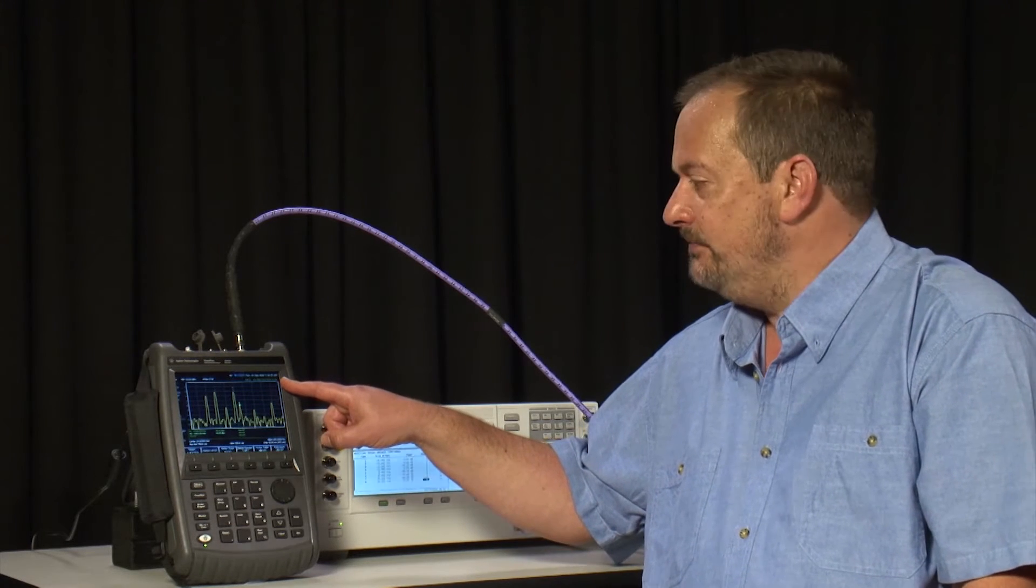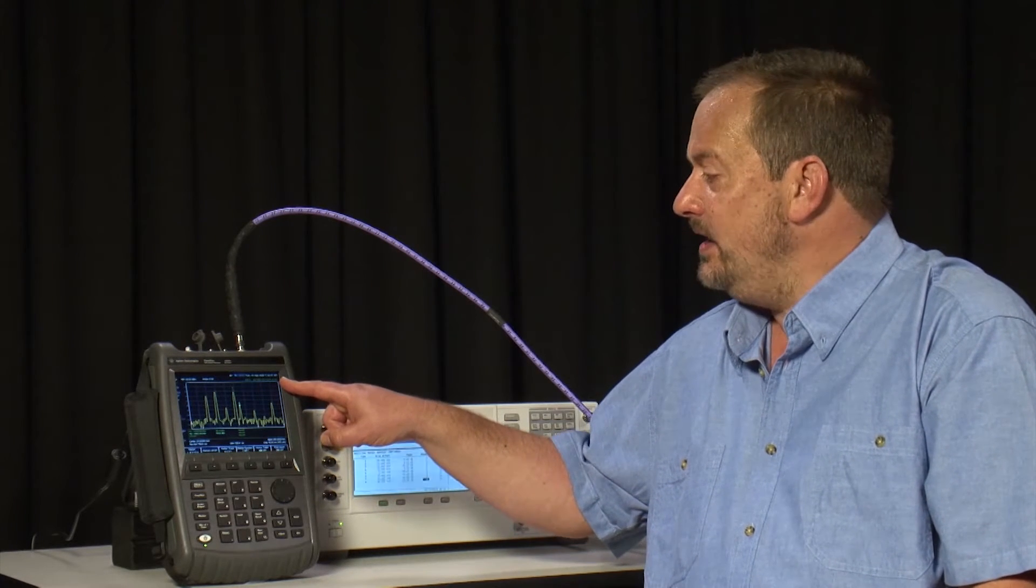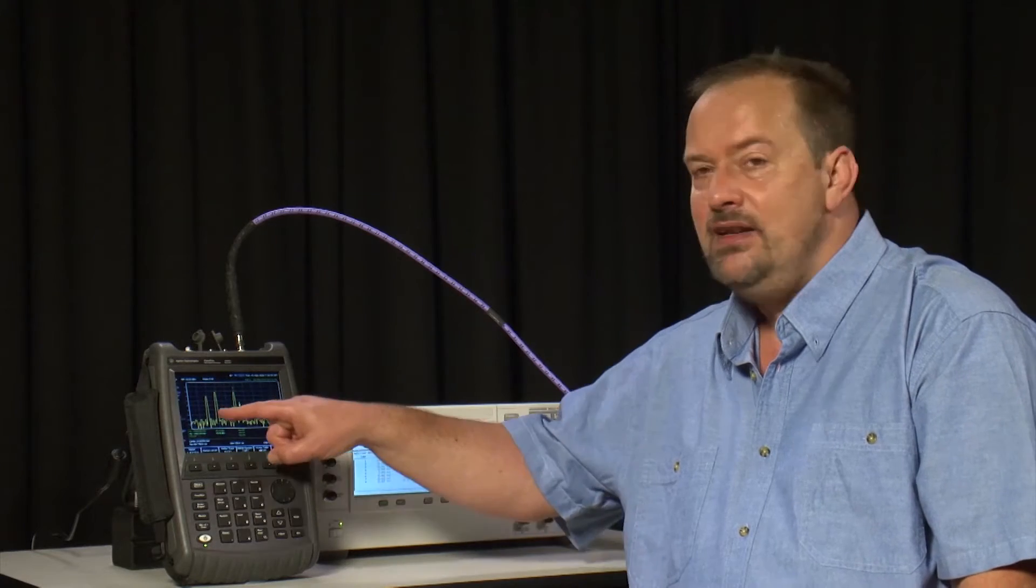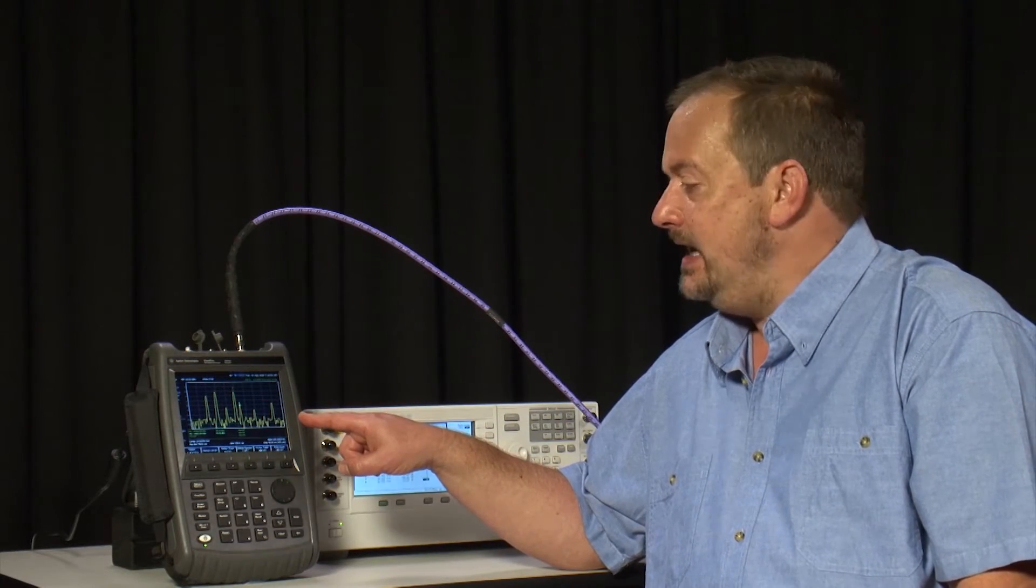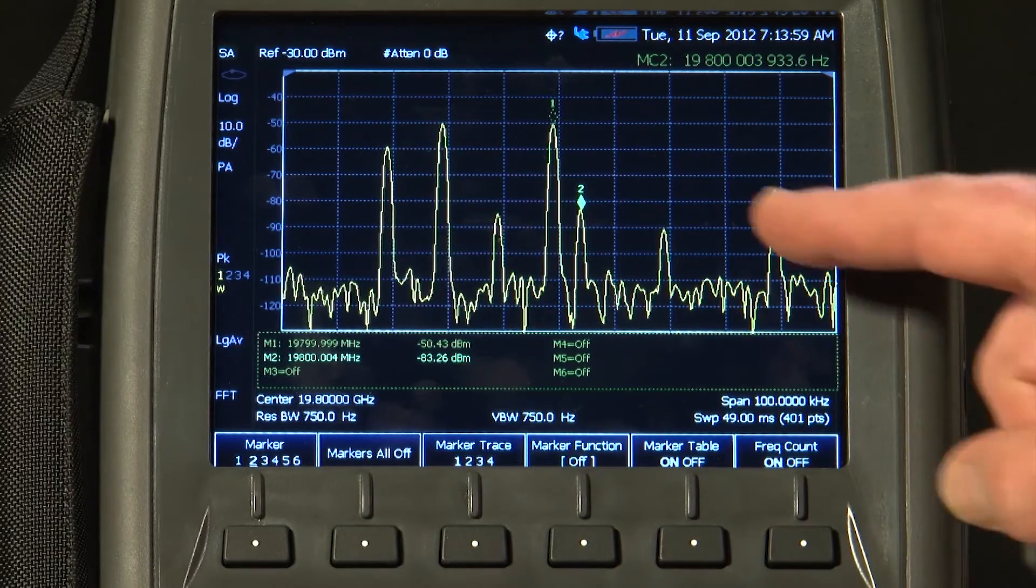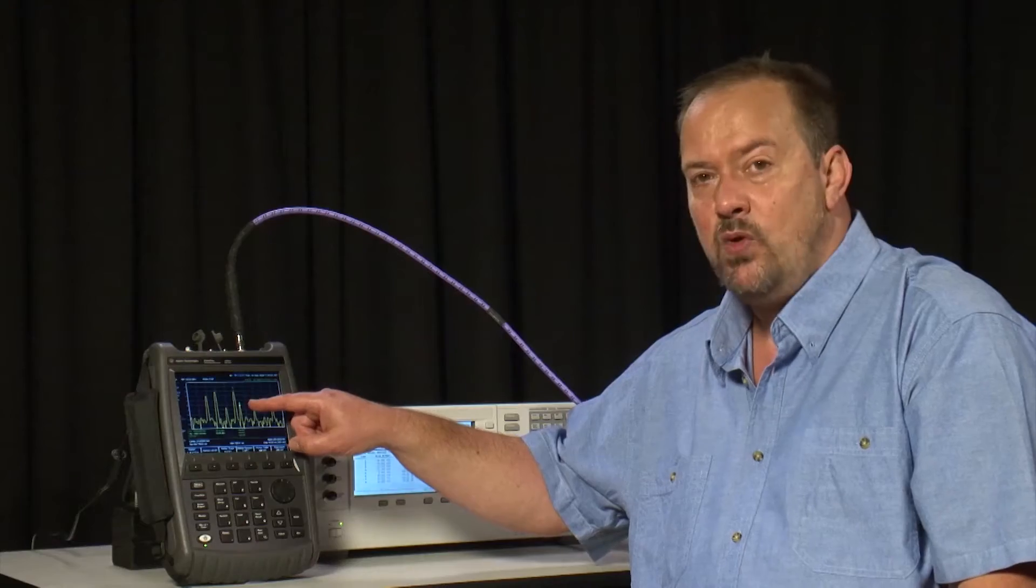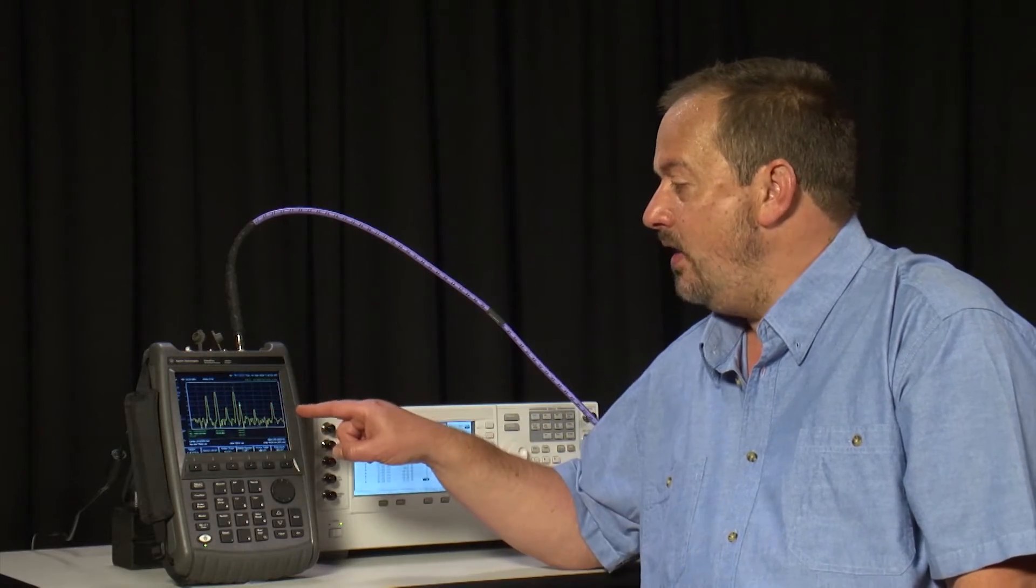But there is one additional advantage. With a normal frequency counter, it can only measure the frequency of a single signal being presented at the input. But with the marker counter function, we can have multiple carriers present and measure the frequency of just one of those, even in the presence of all those carriers.